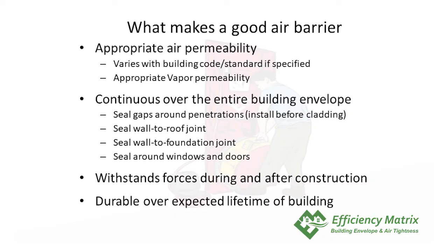If you don't address it in contractual time, you can hardly put a back charge on anyone, and most builders will say it's not their business. So the air barrier needs to seal gaps around every penetration — any pipe, conduit, duct, wall to roof, wall to foundation, around windows and doors. Nothing here is surprising; you just need to think about it methodically.